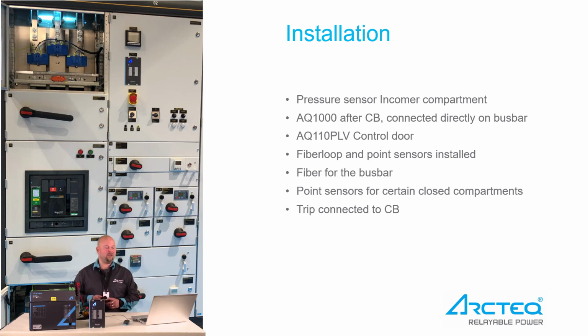And here, if there's a fault anywhere in the board, feeder, anywhere after the circuit breaker, if there's arc flash, then this arc quenching unit will close in less than 4 milliseconds, and the circuit breaker starts to open simultaneously. And that takes typically 30 to even 150 milliseconds. 150 milliseconds is about a blink of an eye.